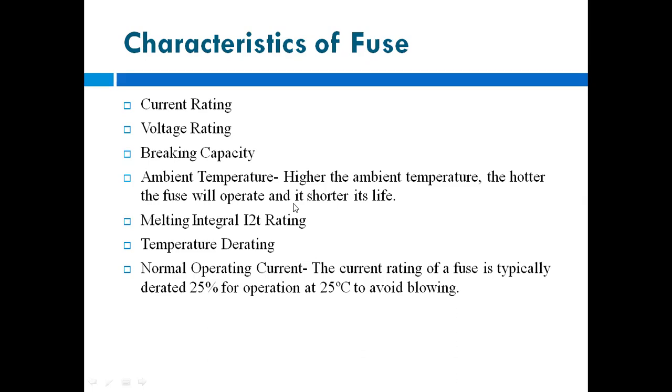At that time, whatever be the temperature of the other parts of the fuse, for example, the fixed terminals, the base of your fuse, and the kit kat contact, the porcelain material's temperature is considered here. That is the ambient temperature of the fuse, the temperature of the other elements of the fuse.